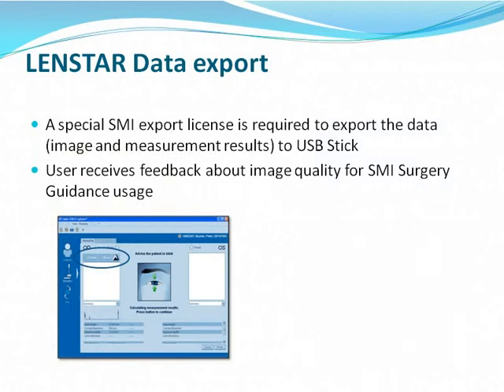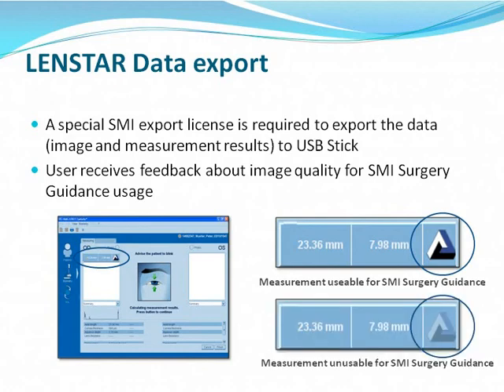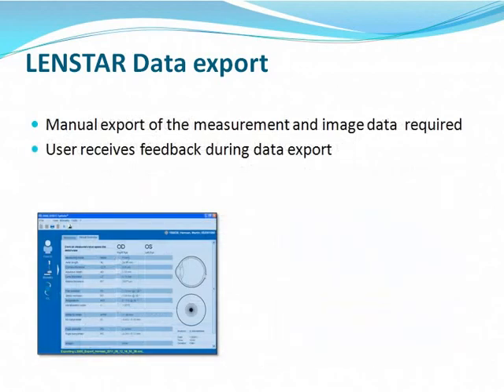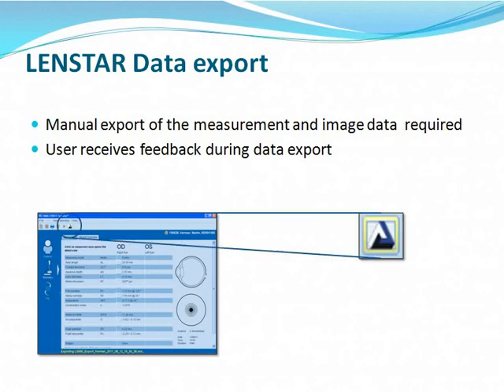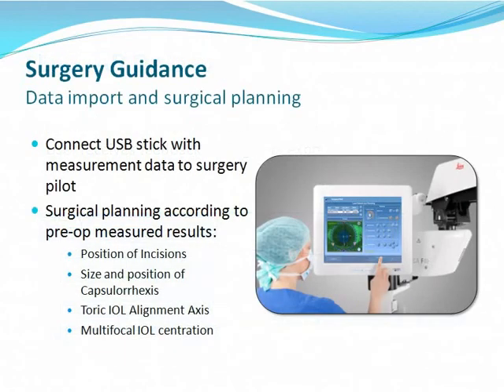You receive feedback concerning the quality of the images you have acquired. If the measurement is usable, you get a blue button; when it's not usable, the button is not highlighted. You can then export all the data acquired, which contains white-to-white measurements and chamber depth as normally acquired with the LENSTAR, and in addition all the digital data on the landmarks of the limbus, iris, and so on. This is transferred as a file that is exported using a USB stick to the surgery guidance feature.